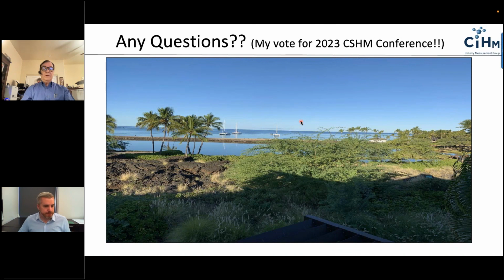Yes, a good question. We ran the meter all the way up until the lower two pairs of transducers stopped working. As soon as we dropped the liquid content, they came back in. At that point, I've got the exact number in a spreadsheet, but both meters, the Orifice and the ultrasonic, were over-registering on the order of around 30 to 35% because of the liquid cross-sectional area causing the gas velocity to read high, and as a consequence, the ultrasonic over-registered, but it was very close to the Orifice meter at that point.